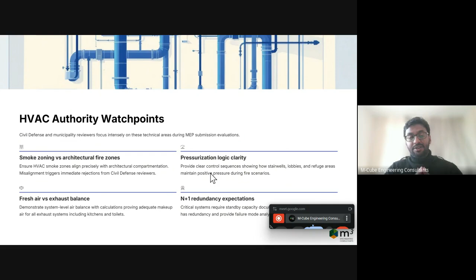Let's take the example of an operation room. There we need to have a redundant system, which is N+1, and we need to ensure this is clearly defined on the drawing. If it's not defined, it goes back and forth and there's loss of time in getting the approval. So certain basic important aspects of design need to be shown on the drawing, so the reviewer can understand the intent of the design and what we're trying to present in terms of compliance with authority requirements.